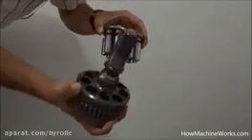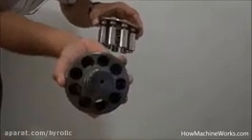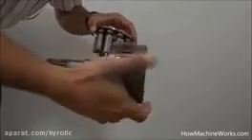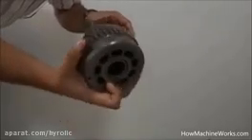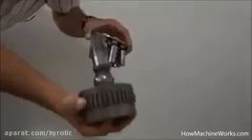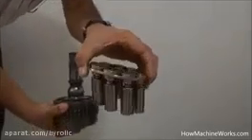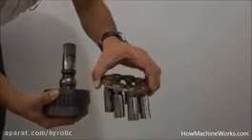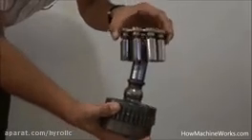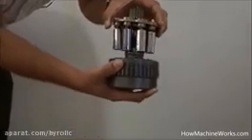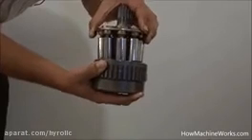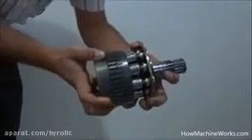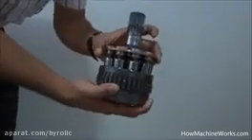Now you can see the pistons which I have shown, and these are the holes where the pistons will actually be inserted, right? Now you can see the cylinder once again at a different angle. Now we'll be putting the pistons back into the cylinder block, and let's see how it can be assembled back. Make sure that once it is removed, each piston is given back into the same port and should not be changed, because they have already mated, and the scoring marks will be like a male-female scoring mark, so it has to be inserted in the same port. So that's how it looks.